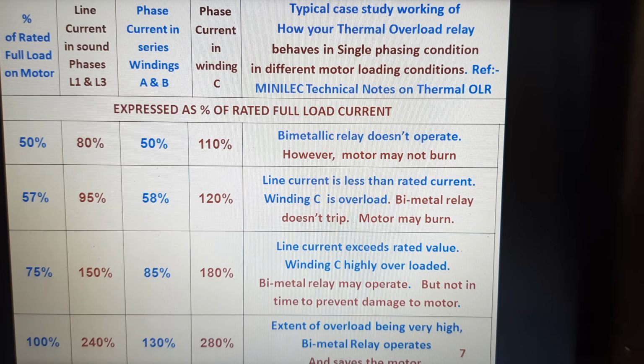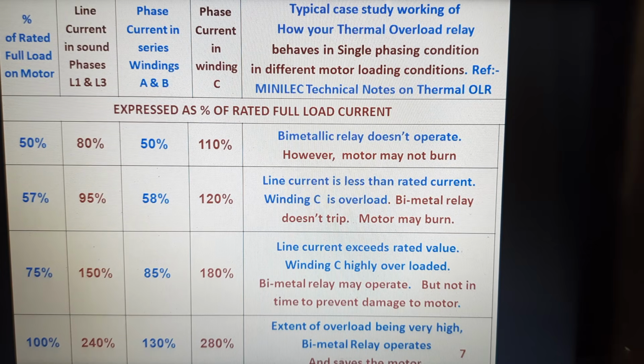At 75% of the motor loading, you can see the line currents on L1 and L3 and the phase currents, but the phase current in winding C has gone to 180%, and the bimetal relay may operate, but it is sluggish to protect the motor, and the motor goes for burnout before the thermal relay operates. At 100% of the motor loading, you can see the phase current in the winding C has gone to 280%. The extent of overload is very high. The bimetal relay will definitely operate and will save the motor at 100% of the loading, but we are mostly running the motors at part loading in our industry, and this is where the electronic overload relay is definitely mandatory for the existing motor applications.